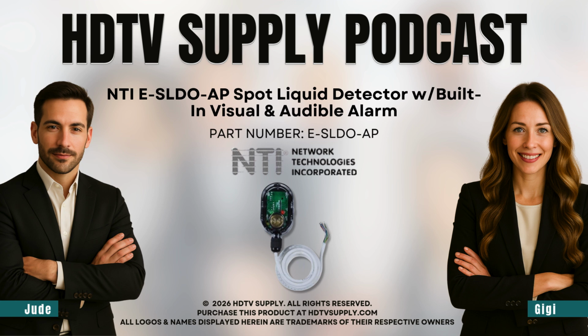And technically, it's made to integrate seamlessly. It has these DPDT alarm contacts, and it's powered by a larger system like the E2D or 5D. DPDT, could you quickly unpack that? Sure, it stands for double pole, double throw. What that means in practice is the switch has 2 separate dedicated paths, so it can do 2 things at once. Exactly, it can simultaneously signal the main alarm system and trigger a totally separate function, like cutting power to the affected equipment. It ensures the response is reliable and immediate.